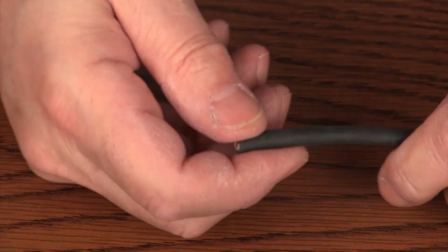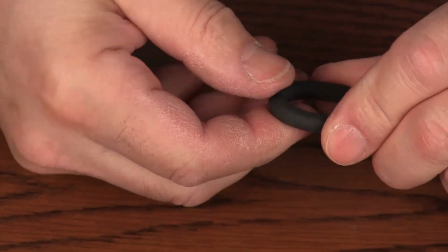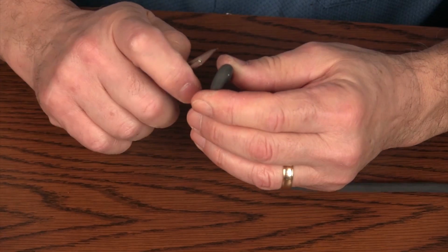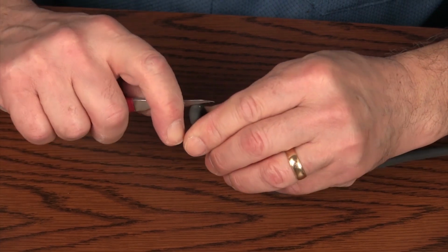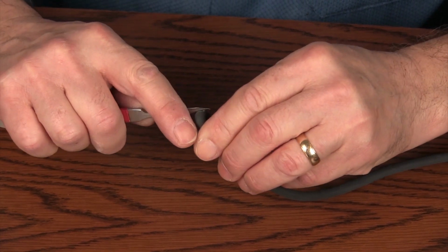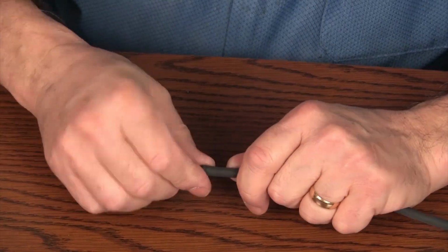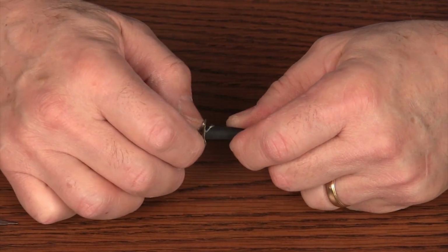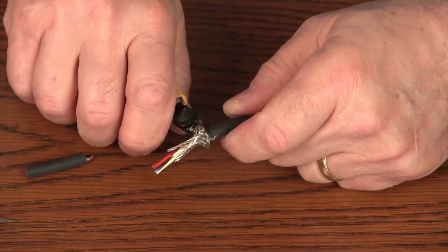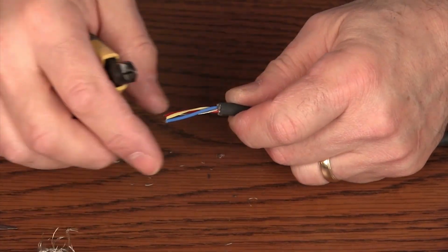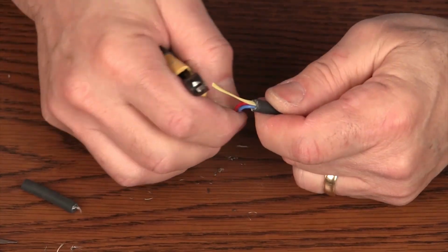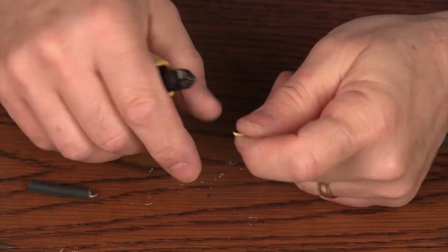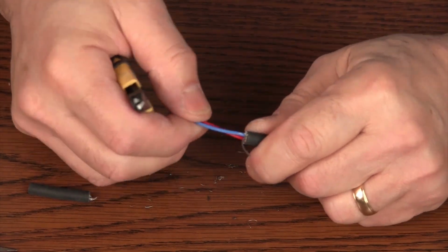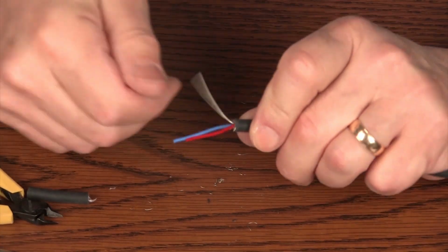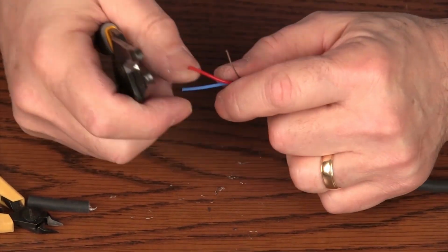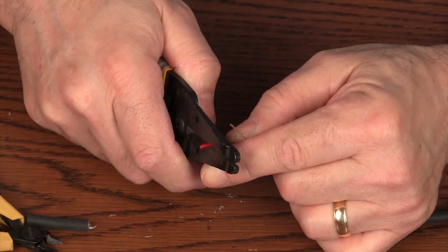Let's review how to create flying leads from a blunt cut cable. In this case, we're using our polyurethane jacketed cable. First, the cable jacket is stripped away. Then the braided shield is pushed back, making it easier to cut away without damaging the conductors. With the shield removed, we can see the positive red wire, which is the signal wire, the blue wire is ground, and the shield drain wire, which also runs the full length of the cable. Next, the sheath over the signal and ground leads is stripped away.